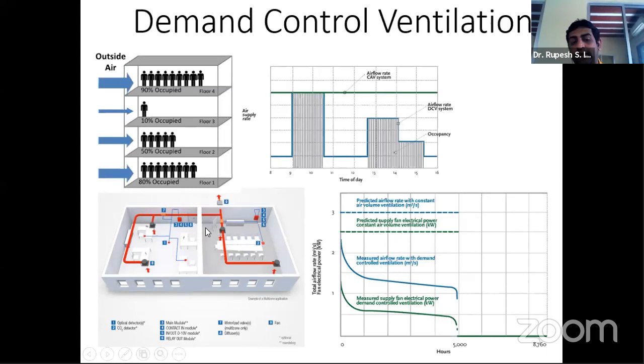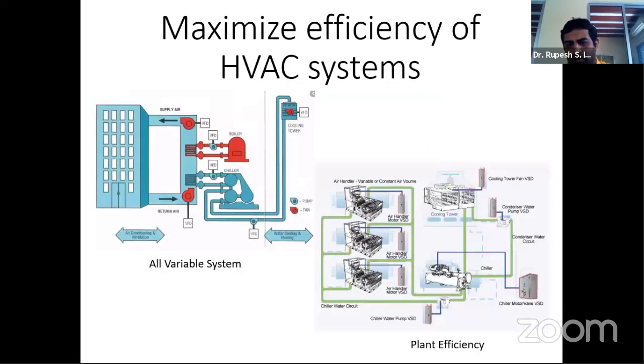So if one room is occupied and another room next to it is having zero occupancy, the air only to the room which is occupied, or having a conference probably, could be supplied with outdoor air. So this is what shows how the demand control ventilation system would work, and it could be linked up to a CO2 sensor or a temperature sensor or a humidity sensor and so on, to make sure there is an effective control on the system. So finally, we are looking at what? We are looking at plant efficiency.